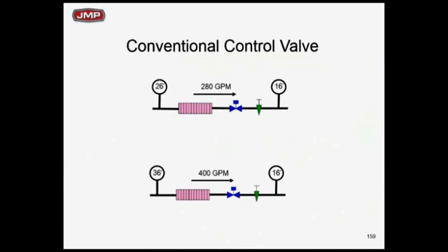So instead of having a high delta T, you got the same BTUs at 280 that you got at 400 GPM. If it's the same load and you increase your flow rate from 280 to 400, what's your delta T got to do? It's got to come down. Q is equal to GPM times 500 times delta T. Then when you have that coming down like that, your delta T has got to come down. You've lost control. You got a chill water plant, you got a return chill water temperature problem. You can't load your chillers up. It's an energy hog. In other words, you're losing delta T because you have a standard two-way valve. You don't have the ability to react that quick.